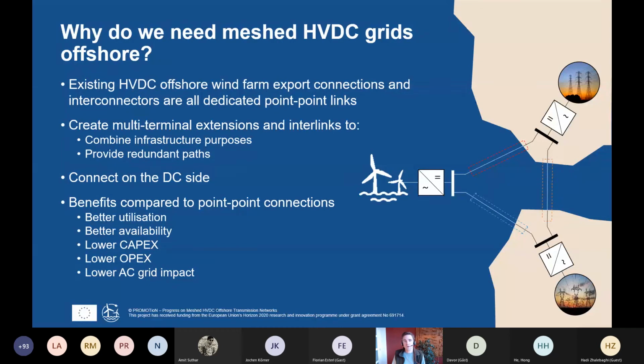Moreover, the offshore wind farms are expected to take over some of the power system stabilizing roles that conventional power plants have today, which requires coordination of their control systems. In addition, to improve the security of supply, an HVDC network protection system must be installed, which continuously monitors the network to detect if and where faults occur. In case a fault is detected, the protection system decides on the best way to disconnect the smallest possible part of the HVDC network that contains the fault.